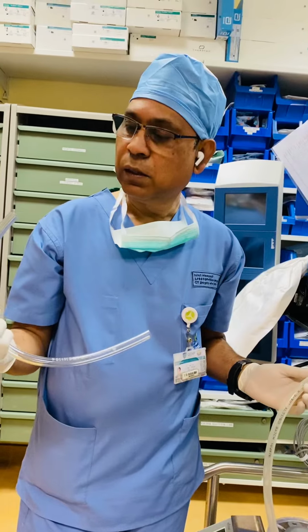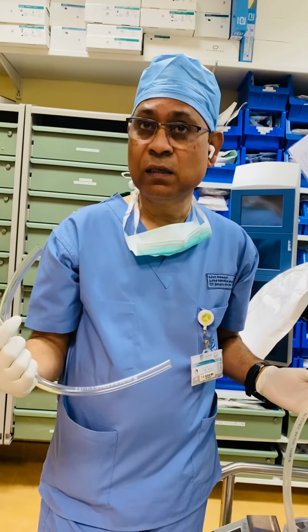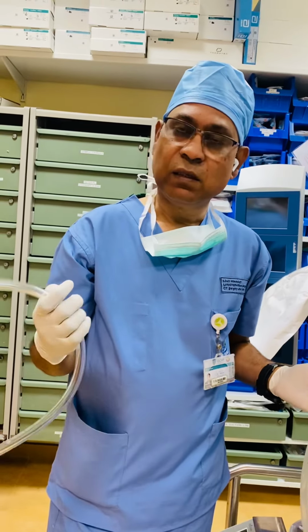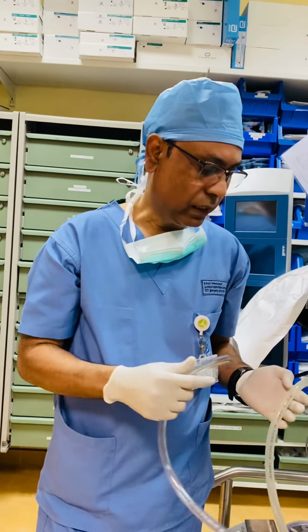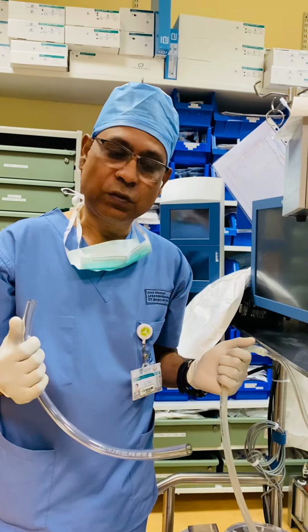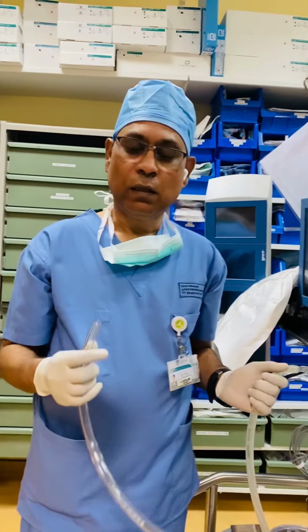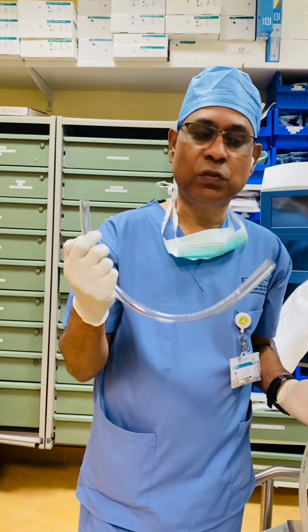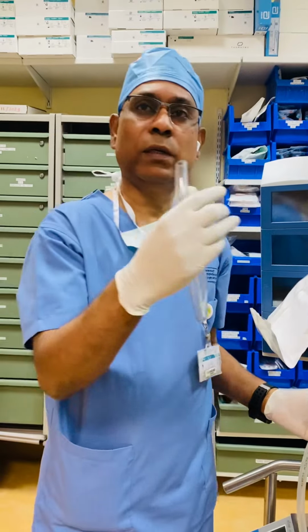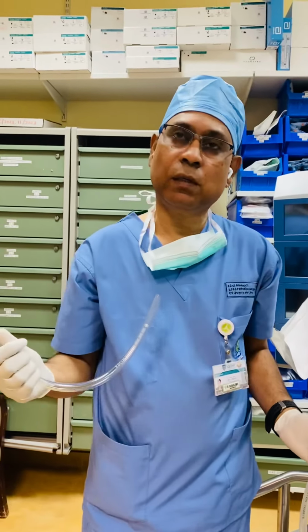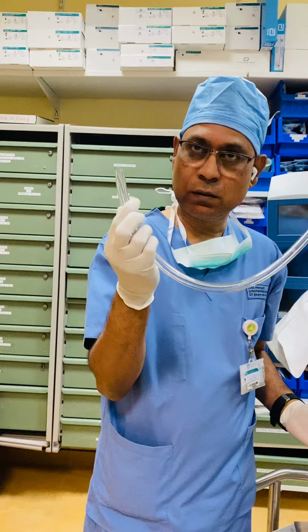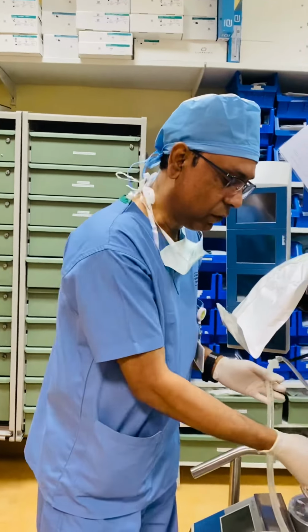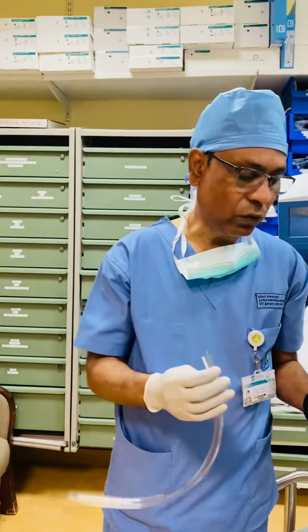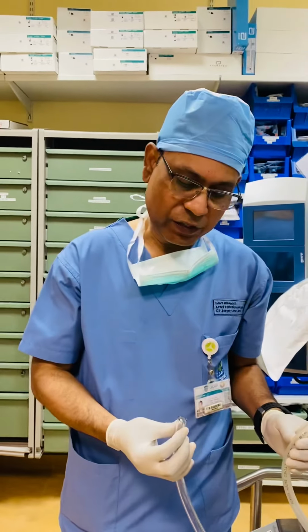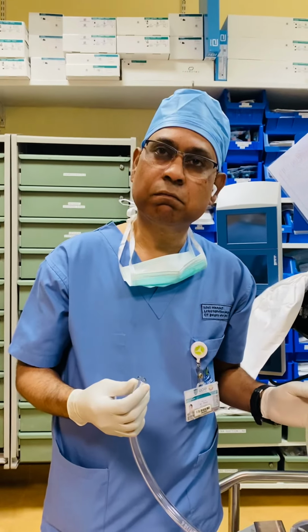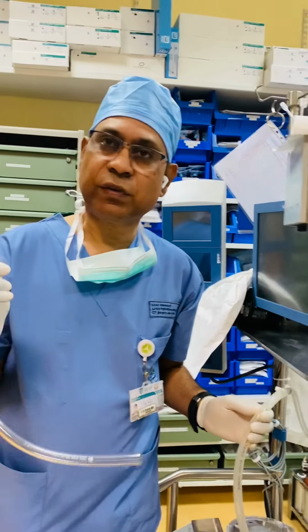In this we have different sizes and different types of tubes. Normally the silicone is used in the roller heads and PVC is used for carrying blood to the body and taking blood back from the body. Why are we not using the PVC tube in our roller head? If you come near and see the material, this one is flexible and this one is rigid.